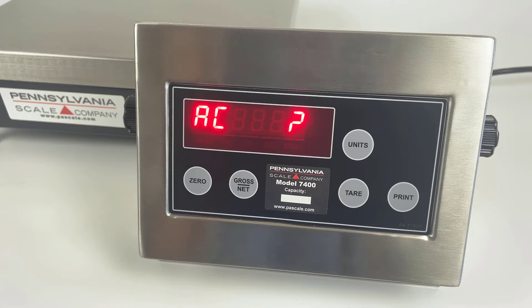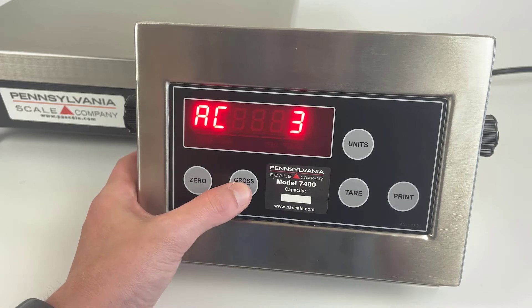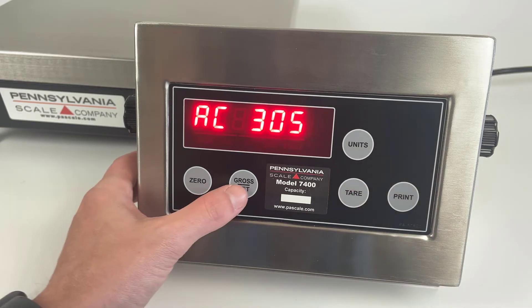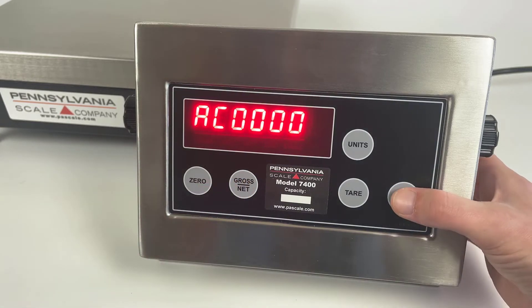The default code is four zeros. If you've changed it, you can use the gross net and tare keys to increase the values as shown. For the default four-zero code, press the gross net key four times.